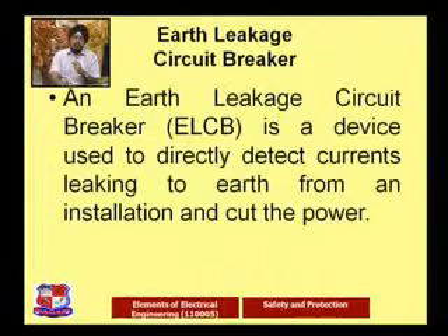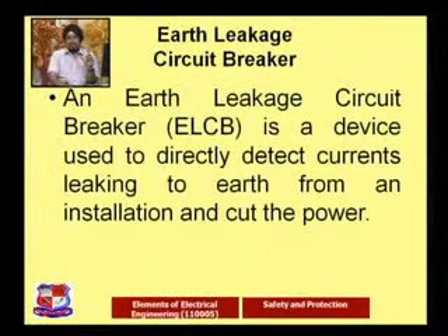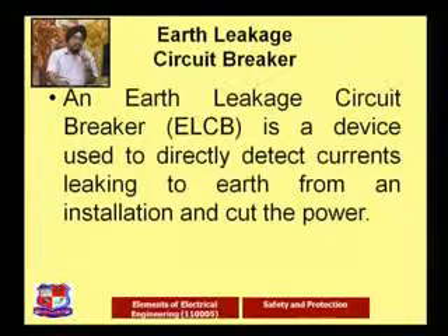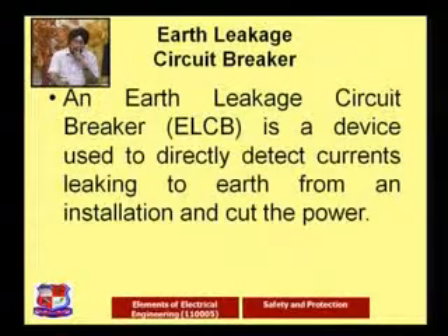Next, we have talked about the protection of the circuitry, but we haven't talked about what happens if there is a fault with respect to earth. To detect that, a protective device known as the earth leakage circuit breaker, ELCB, is used. The ELCB is directly connected with the current leaking to the earth, meaning this device connects to whatever earth wire is there.